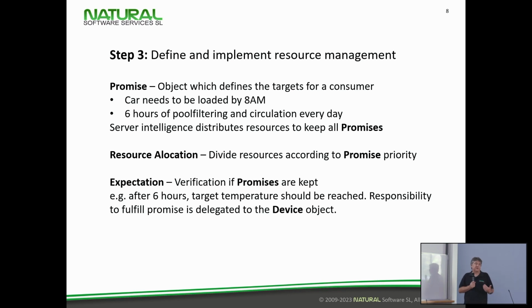These promises, of course, also have priorities. Your pool has to be cleaned every day, has to be filtered. But for example, if you have a hot water deposit, the Legionella program only needs to be run once a week. On Friday, it's becoming urgent. On Monday, the system really doesn't care.